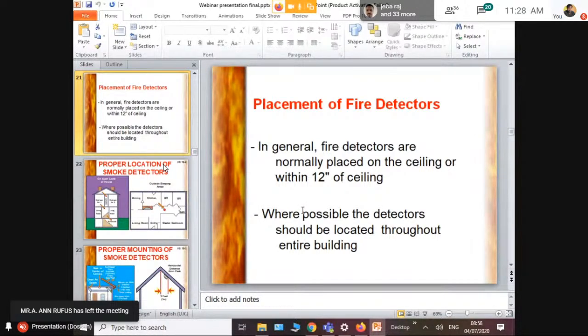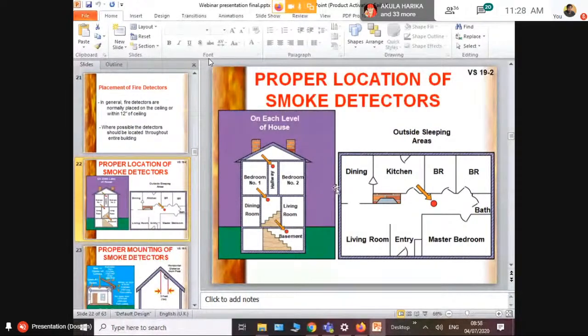The next point is that it is advisable to have smoke detectors all around the building. I'll show you a small pictogram of how and where we can install them. This is a plan of the same house. This is a hallway, so it's better to have a smoke detector in this area. In the kitchen, we have to install a heat detector. In the dining area, we can install a smoke detector. In bedrooms, it's advisable to have smoke detectors. In the bathroom, preferably install nothing because it is prone to water, but there are devices suitable for bathroom setups as well. It depends on the client's funding for the project. In the master bedroom, you will again prefer a smoke detector.